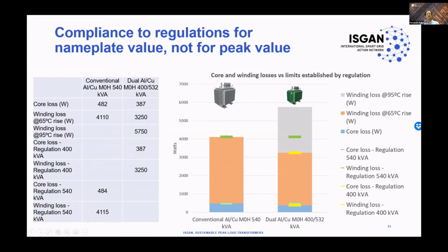If we represent in this graph the limits imposed by the European regulation, we have the core losses. For this, we have represented in blue the core losses. Then this unit would be compliant with it, and also with the winding losses. And this is the limit in green here. Let me maybe put the pointer. Yeah, so here, this unit, the conventional unit, of course, complies with the regulation.